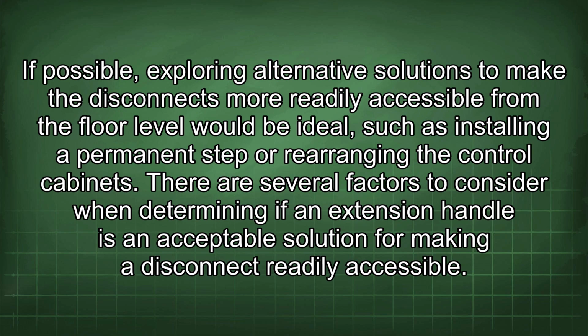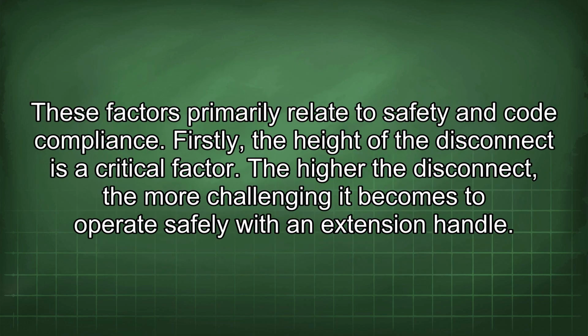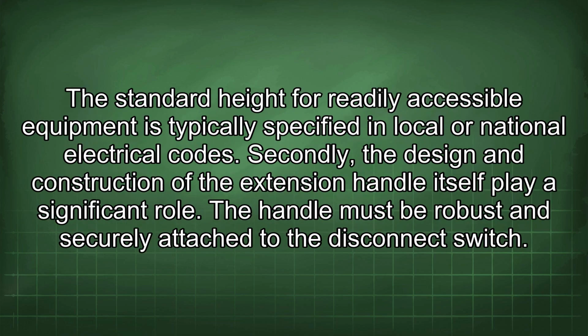There are several factors to consider when determining if an extension handle is an acceptable solution for making a disconnect readily accessible. These factors primarily relate to safety and code compliance. Firstly, the height of the disconnect is a critical factor. The higher the disconnect, the more challenging it becomes to operate safely with an extension handle. The standard height for readily accessible equipment is typically specified in local or national electrical codes.